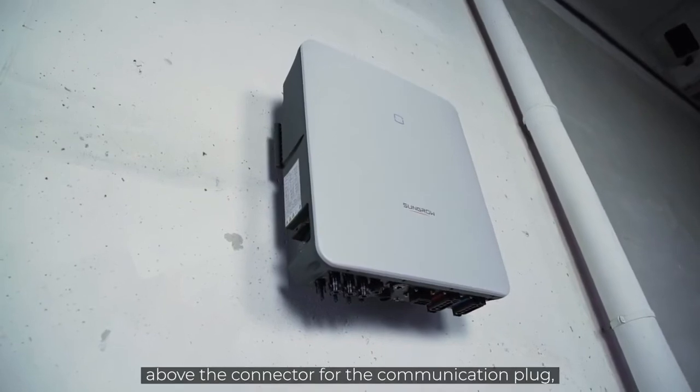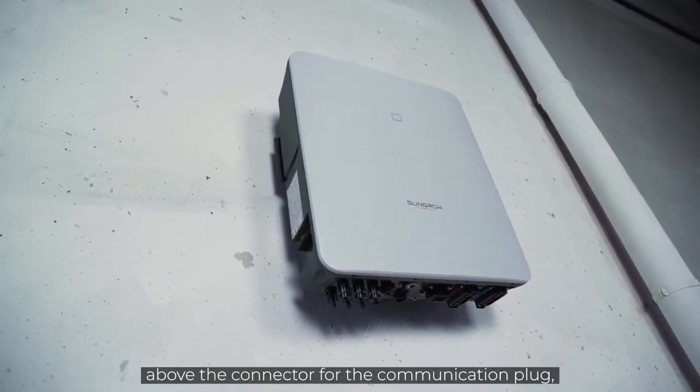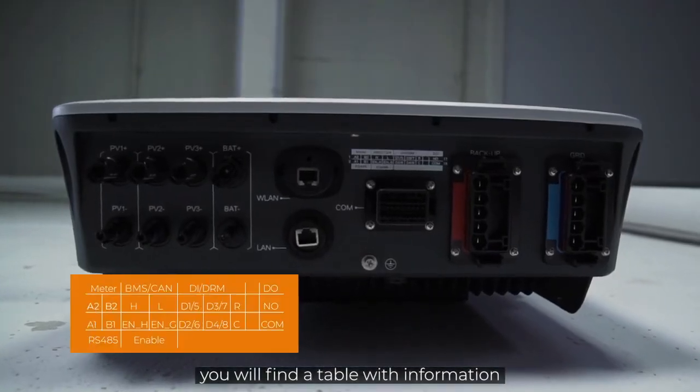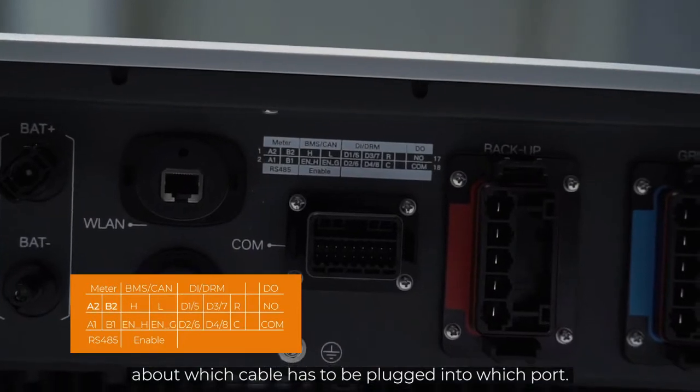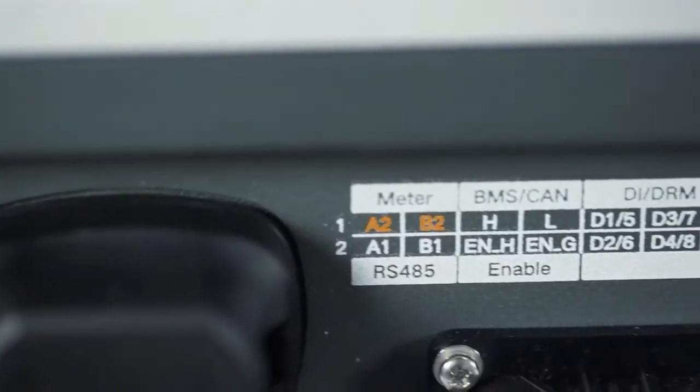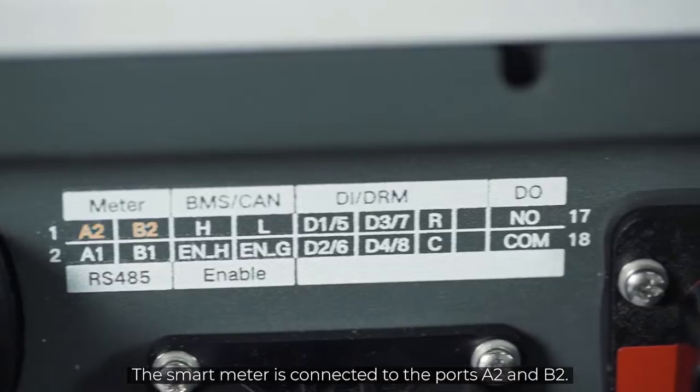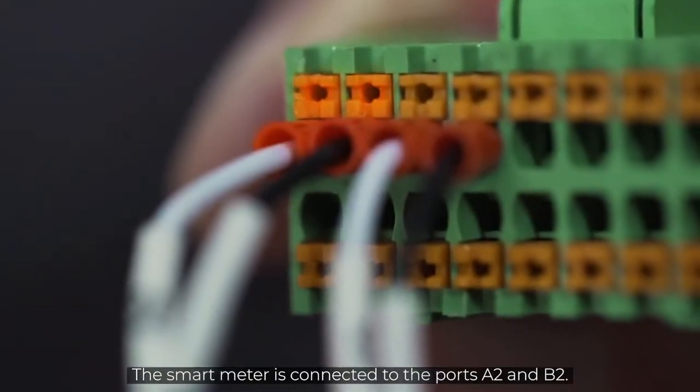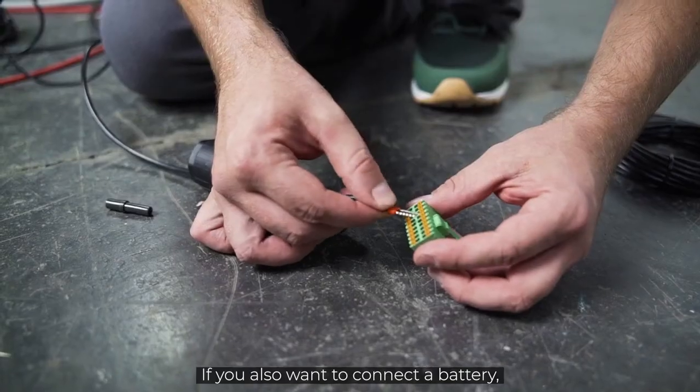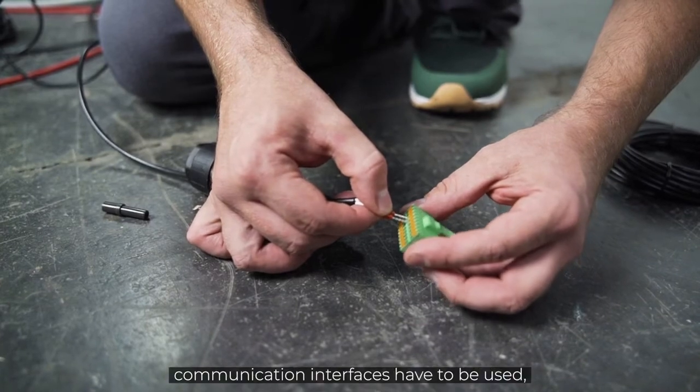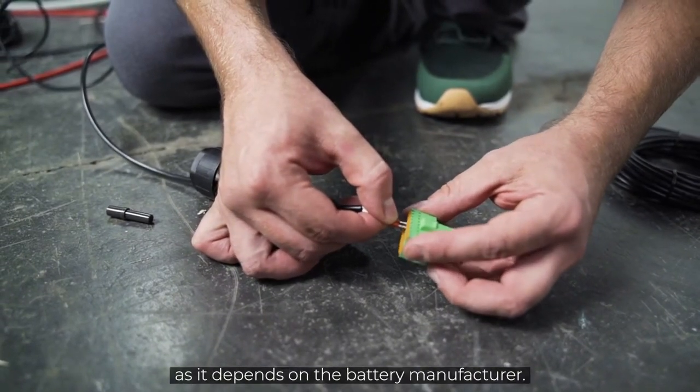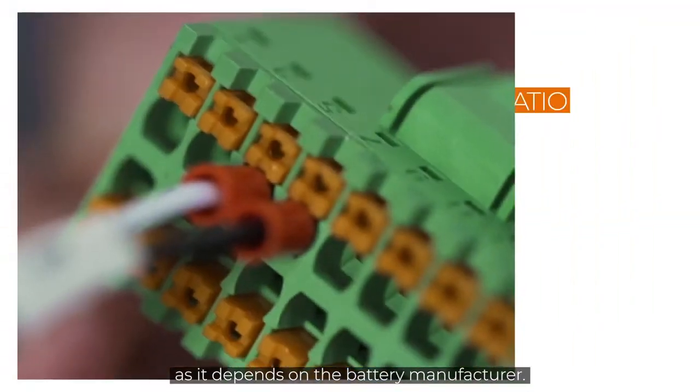At the bottom of the inverter, above the connector for the communication plug, you will find a table with information about which cable has to be plugged into which port. The smart meter is connected to the ports A2 and B2. If you also want to connect a battery, you need to pay attention which communication interfaces have to be used as it depends on the battery manufacturer.